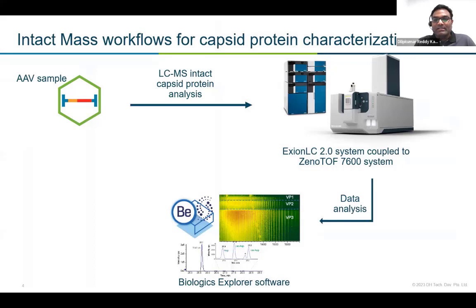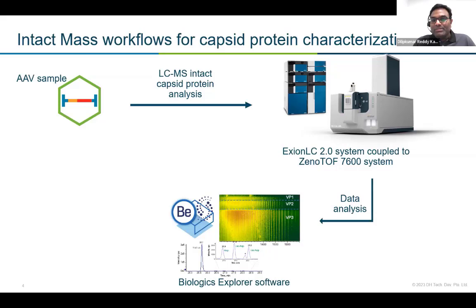Let's begin with the intact protein molecular determination using the SciEx ZenoTOF 7600 instrument. Here you can see the high-level schematic of the intact mass determination workflow for capsid protein characterization. For intact mass analysis, sample preparation is very fast. It involves a first step of denaturation to break apart the capsid, followed by a buffer exchange to remove buffer components that could interfere with ionization on the mass spec. We have implemented an LC approach with analytical flow connected with the ZenoTOF 7600 system to acquire the data sets, then processed them using software called Biologics Explorer. I'd like to switch to the SciEx OS software to demonstrate how easy it is to set up the method for determination of the molecular weight of the AAV8 capsid protein.